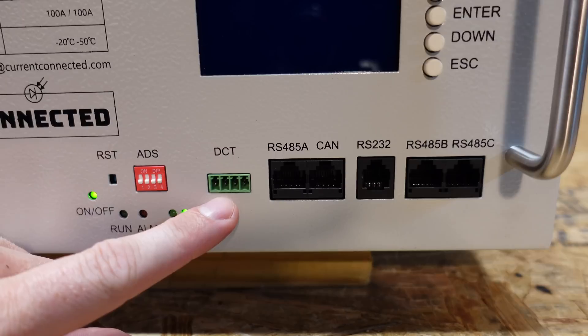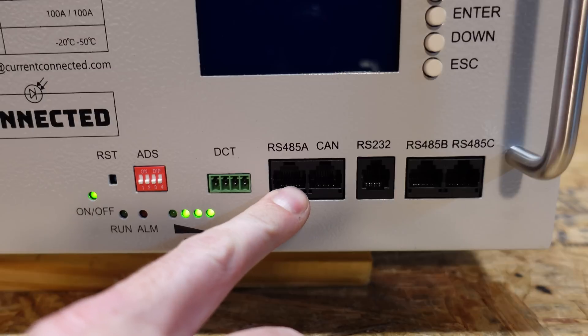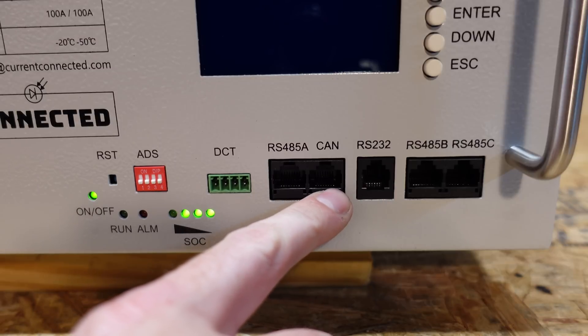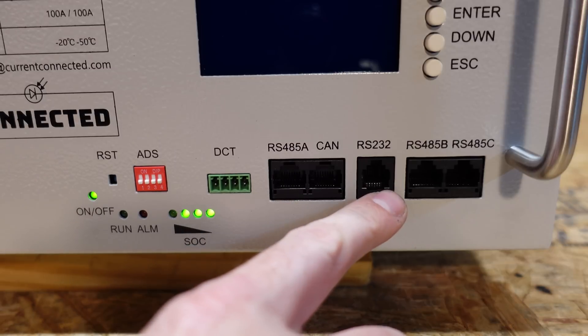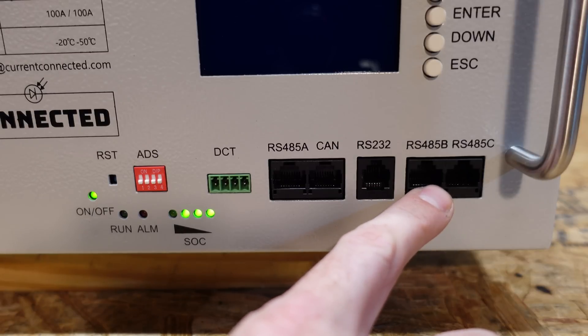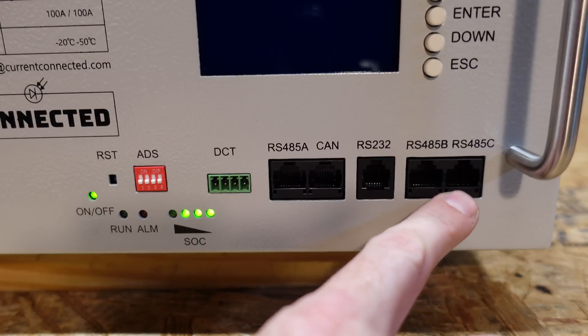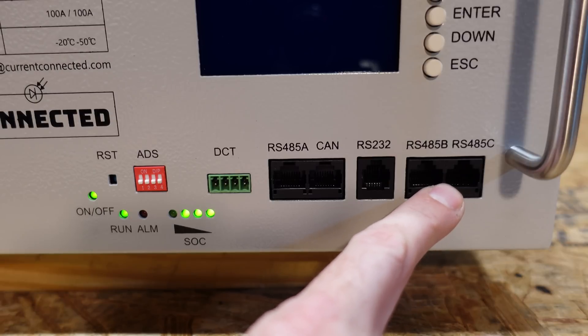The DCT port is a dry contact relay. RS-485A is for communications to your inverter. We have a CAN port that's also for communications to your inverter. We have an RS-232 for communications to your computer. And we have RS-485B and C, which are used for chaining multiple batteries together so the batteries can communicate with one another.